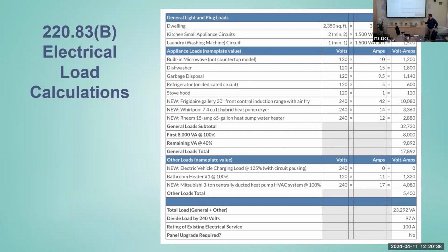Then we move on to the next section, which includes all the loads the code says we have to put as 100% coincident. In other words, we just assume they're always on, because they're usually higher-utilized loads with the potential to run longer cycles. It all comes down to trying to avoid heating up the wires and bus bars and causing fires.